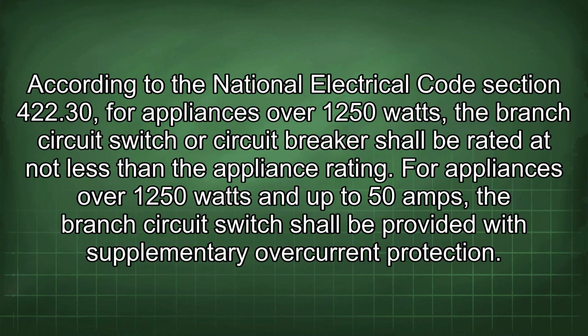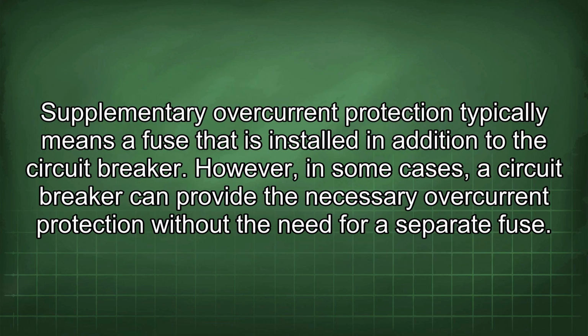According to the National Electrical Code Section 422.30, for appliances over 1250 watts, the branch circuit switch or circuit breaker shall be rated at not less than the appliance rating. For appliances over 1250 watts and up to 50 amps, the branch circuit switch shall be provided with supplementary overcurrent protection. Supplementary overcurrent protection typically means a fuse that is installed in addition to the circuit breaker.